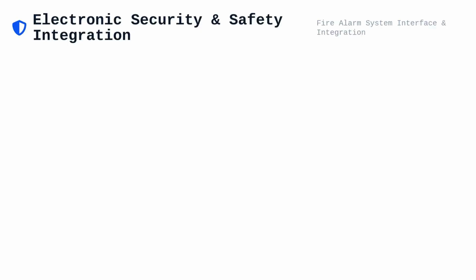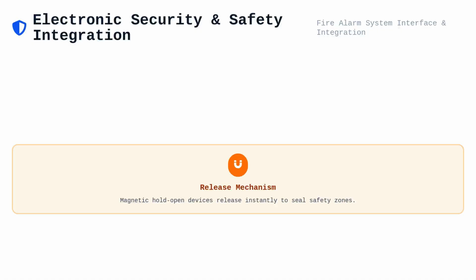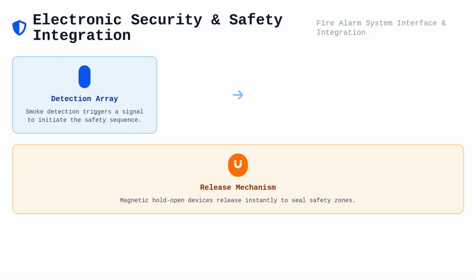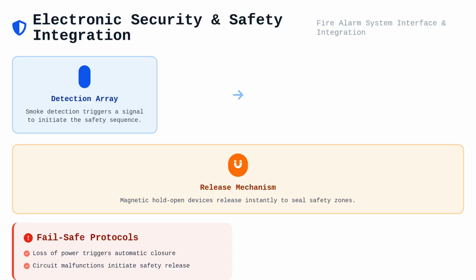Integrating electronic security and safety features into these assemblies requires close attention to the interface between hardware and the fire alarm system. Magnetic hold-open devices are commonly utilized for convenience, allowing doors to remain open during normal operations while ensuring they release instantly when a smoke detection array triggers an alarm. The reliability of this integration depends on the interaction between the detection signal and the release of the door closer, or electromagnet. It is imperative that these systems remain fail-safe, meaning that a loss of power or a malfunction in the detection circuit initiates the closing process.